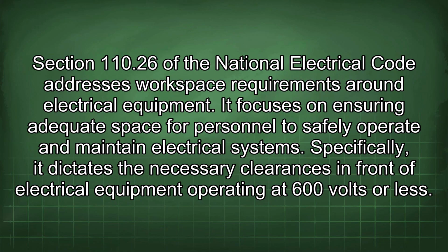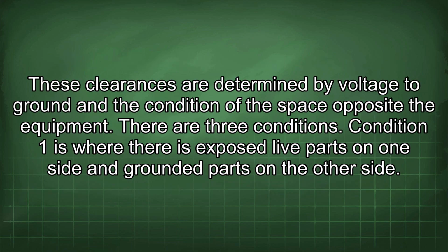110.26 of the National Electrical Code addresses workspace requirements around electrical equipment. It focuses on ensuring adequate space for personnel to safely operate and maintain electrical systems. Specifically, it dictates the necessary clearances in front of electrical equipment operating at 600 volts or less. These clearances are determined by voltage to ground and the condition of the space opposite the equipment.